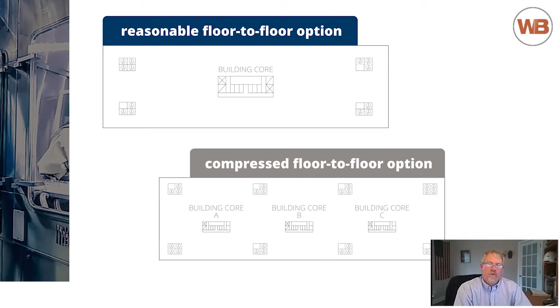We talked a bit about fire separation and having the exhaust separated in the prior diagram. The important thing to understand is that a 2-hour rated enclosure is needed for each fume hood exhaust system, or hazardous exhaust system, feeding each floor, in a dedicated riser from the floor it serves all the way to the penthouse or roof. In the diagram, you can see how individual shafts with 2-hour rated separations give you a duct from each floor to the roof or penthouse.